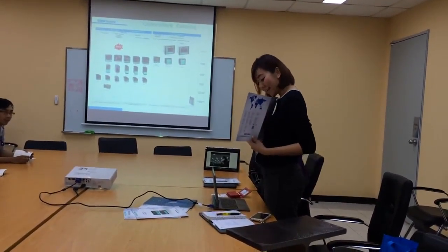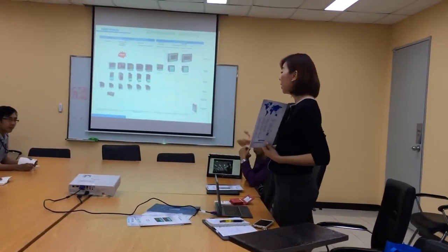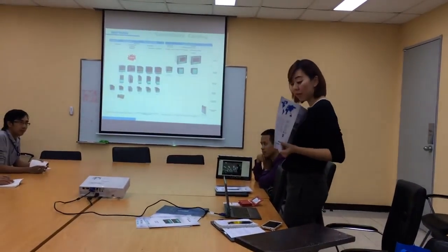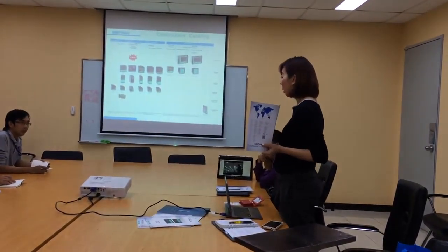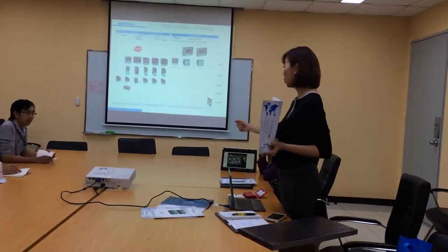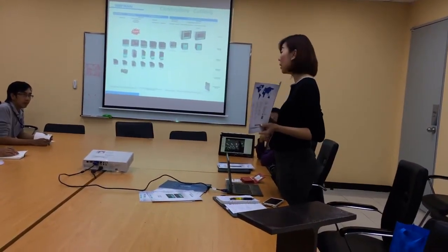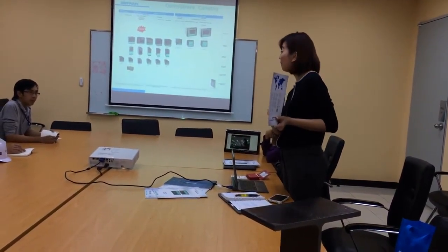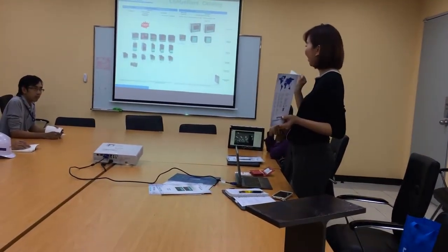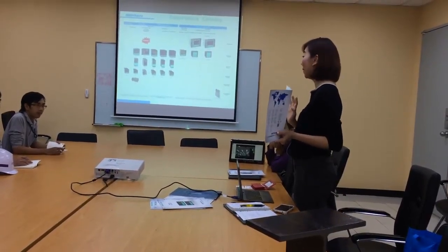Another thing is that if you want to use your computer to program, it uses the same software as our drive, GEFRAN. With GEFRAN, you can program the controller without powering up. Normally, with other temperature controllers, you need to put in power, then you do programming. For ours, you do not need to. You can just plug a cable from the controller to your laptop, and it will take the power from the laptop. So you do not need external power.